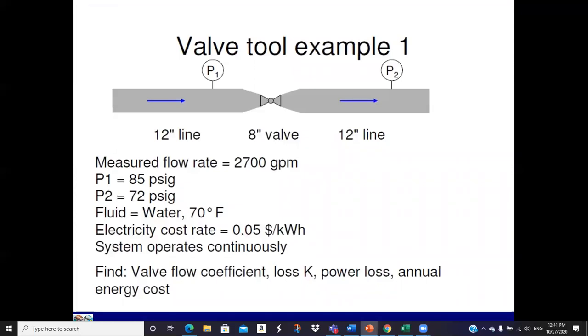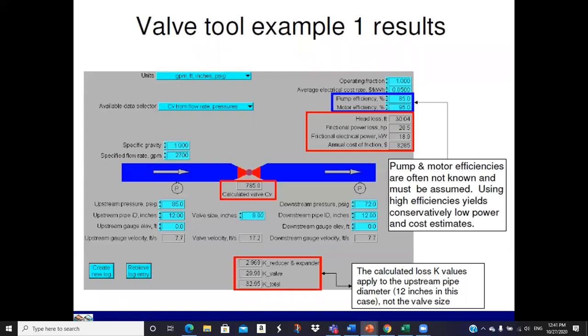So here's some examples. This is 12-inch pipe, 8-inch valve, measured flow rate 2,700, upstream pressure 85, downstream 72. We've got pretty standard water at 70 degrees Fahrenheit, 5-cent power, and it operates all the time. So we want to find the valve flow coefficient, the loss factor K, the power loss, and the annual energy cost. So there you go.